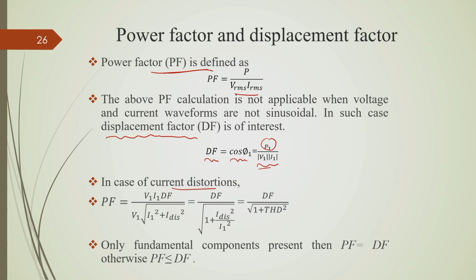And when we have distortion in the currents, then the power factor is basically the displacement factor divided by 1 plus THD I. Similarly, if we have distortion in the supply voltage, it will also be a function of THD V as well. Okay. And the actual power factor is lower than the displacement factor, that one should know.